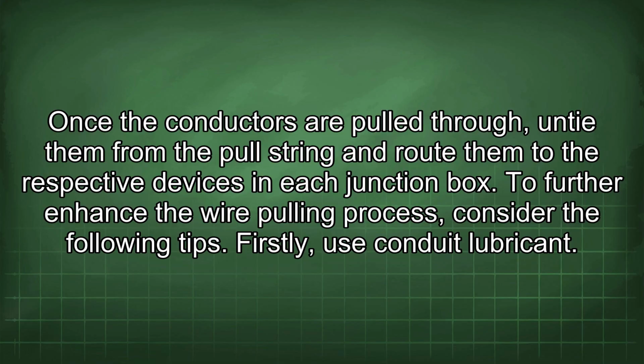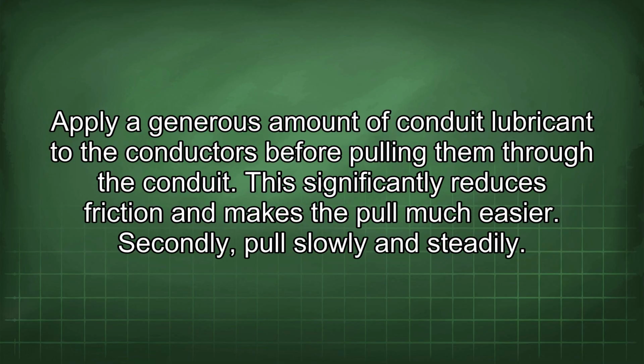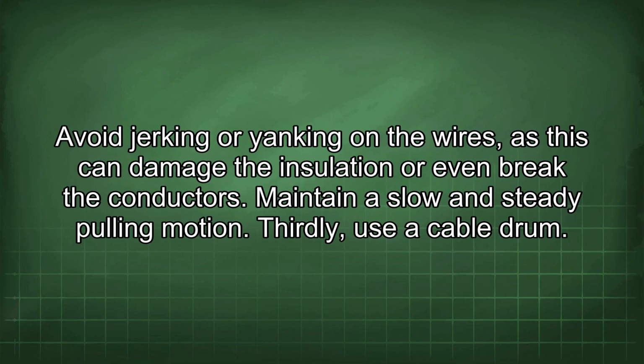To further enhance the wire pulling process, consider the following tips. Firstly, use conduit lubricant. Apply a generous amount of conduit lubricant to the conductors before pulling them through the conduit. This significantly reduces friction and makes the pull much easier. Secondly, pull slowly and steadily. Avoid jerking or yanking on the wires, as this can damage the insulation or even break the conductors. Maintain a slow and steady pulling motion.